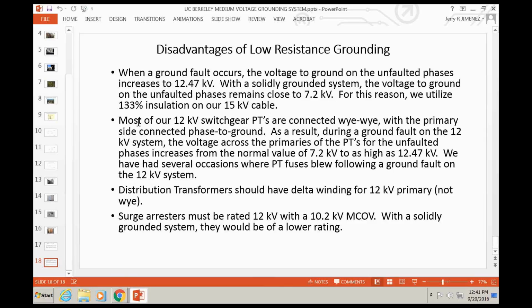Okay, so here's another one that you don't see in any books. We had a pretty serious ground fault here about 2 or 3 years ago. It went on for a while, probably 1.5 seconds, and it was pretty hefty. It was up close to our transformers. We got that all figured out and addressed. But a few days later, some of our metering was reading incorrectly on our 12 kV system. Come to find out, we had blown a lot of primary fuses on our potential transformers.